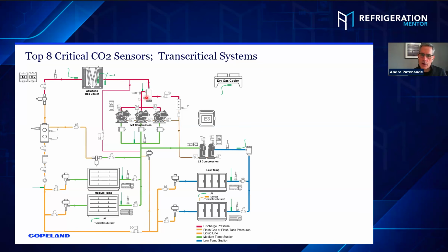I've got my oil separator with a low level switch, discharge pressure transducer, temperature sensor, solenoid valve, oil solenoid valve. I've got an oil reservoir, so I've got a low pressure oil system with its own level control and oil system to the low temp. I'm using an adiabatic gas cooler in 95% of my images because 95% of the gas coolers that are out there today, especially in the US, are adiabatic.